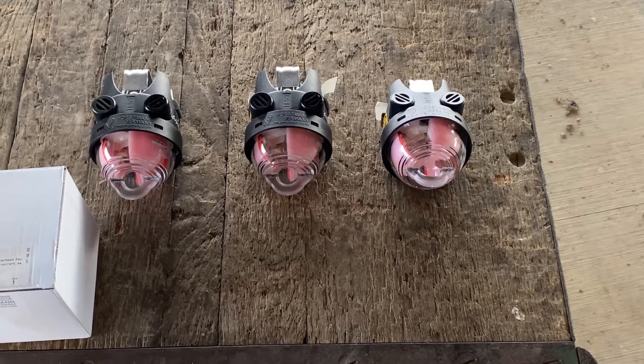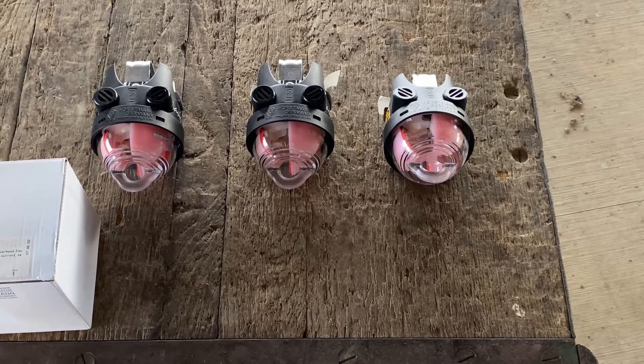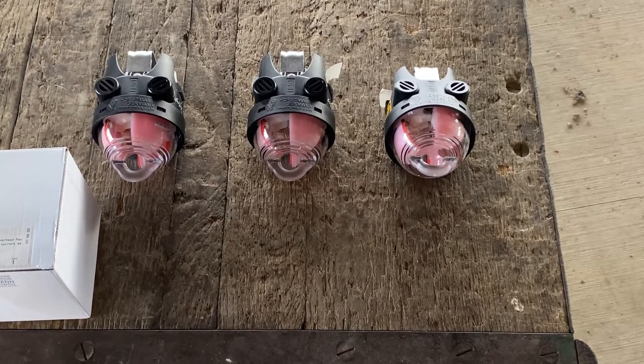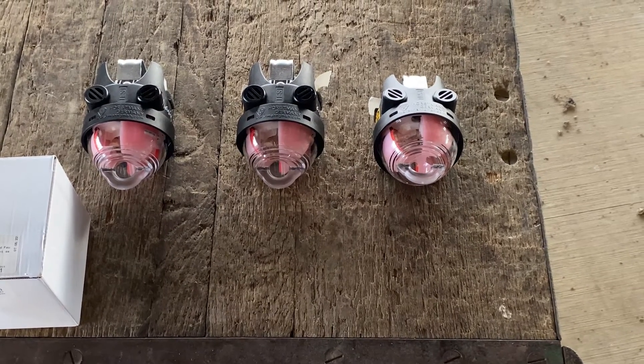On a permanent fault, these will come back and blink for four hours, and then after four hours the red flag will stay down for two days. So we're going to test these now.